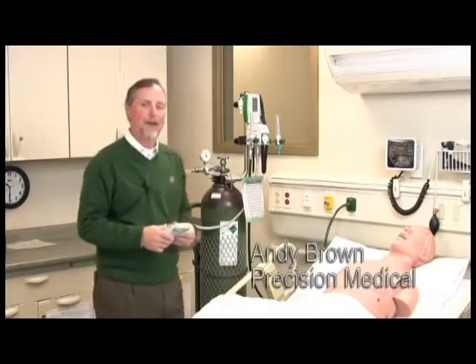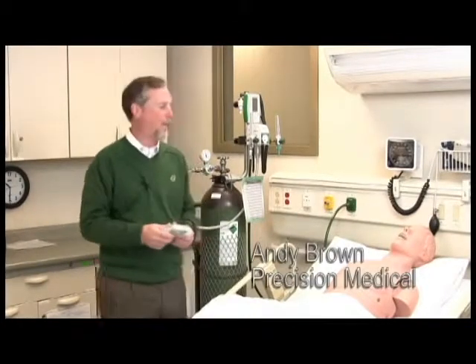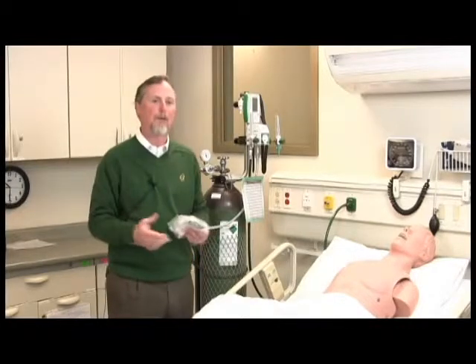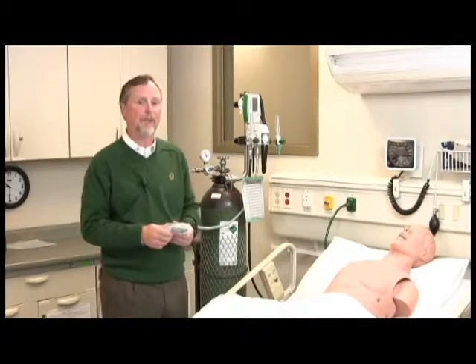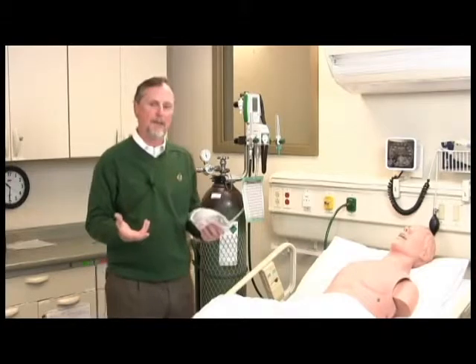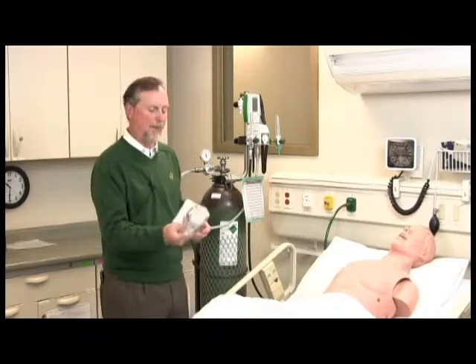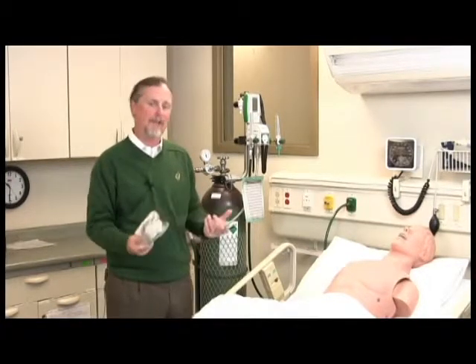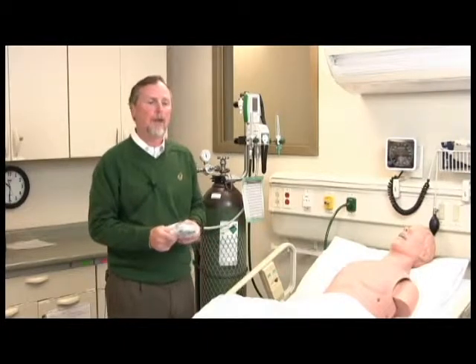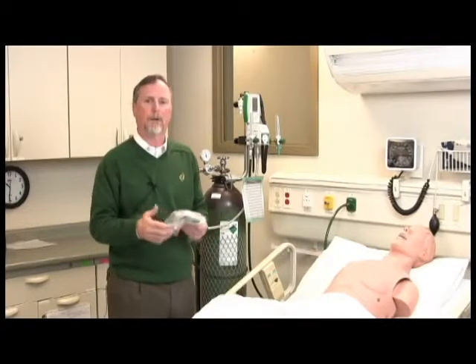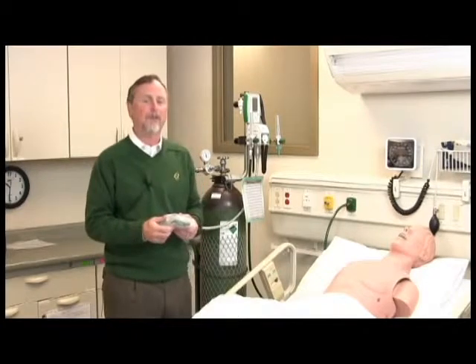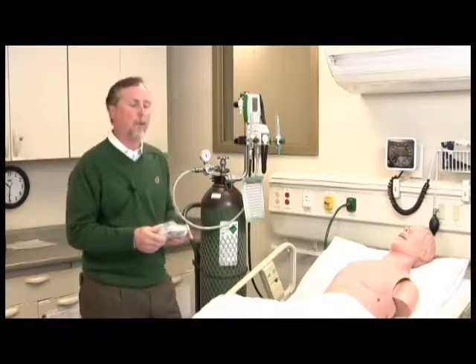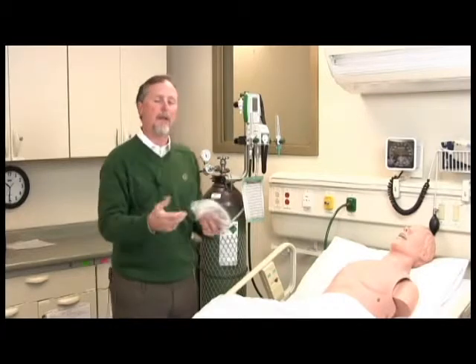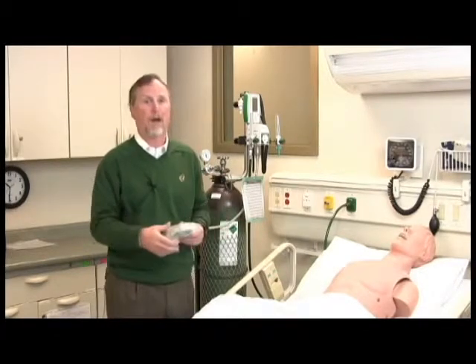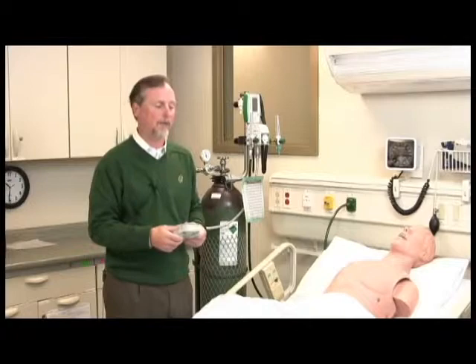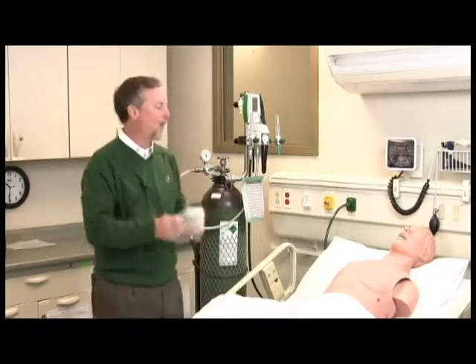Okay, now we're going to talk about initiation of Heliox therapy. The most common way of doing Heliox therapy is via a high flow system, to meet the patient's inspiratory demand. In this example we have a non-rebreather, although there's evidence out there for other devices to be used. We do caution people and advocate that you use Heliox on label, so that whatever you hook up to the Heliox blender is a device that is approved for Heliox use or has been tested with Heliox through it. So in this case we have a non-rebreather.